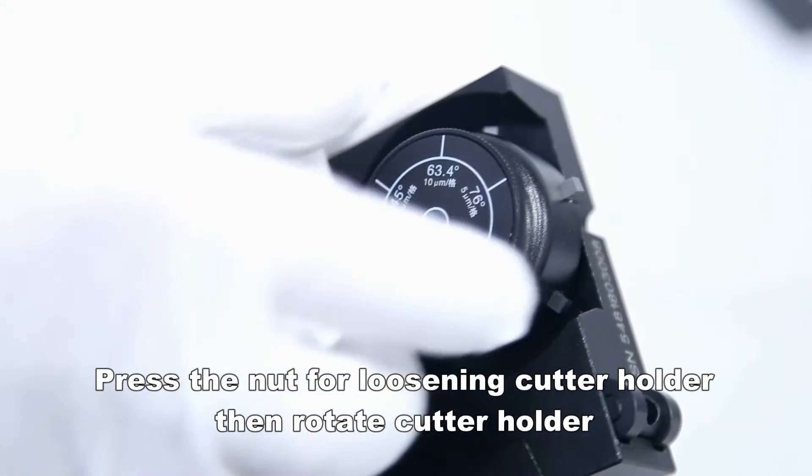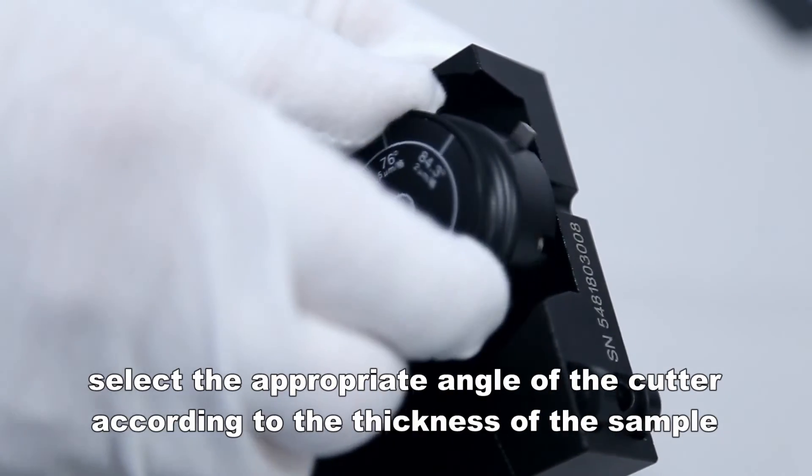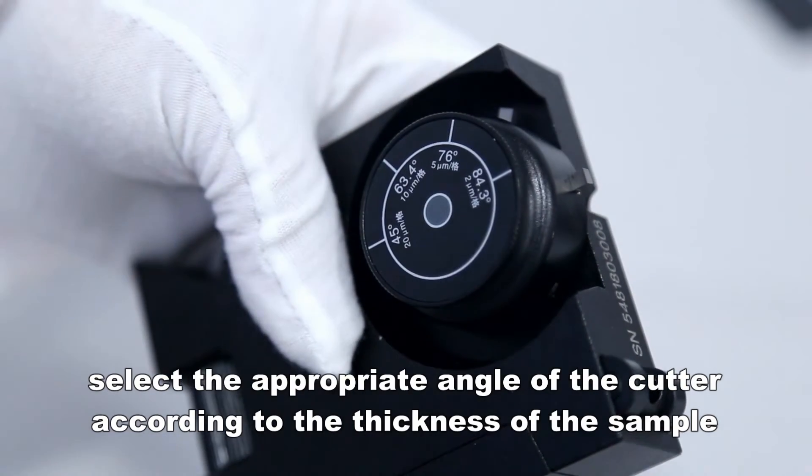Press the nut to loosen the cutter holder, then rotate the cutter holder. Select the appropriate angle of the cutter according to the thickness of the sample.